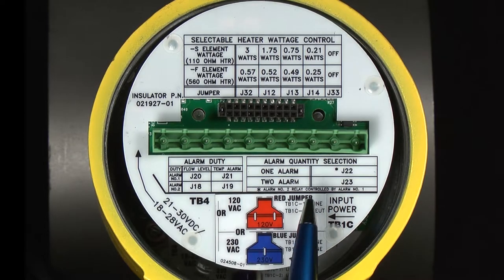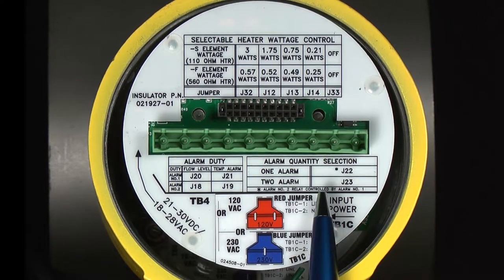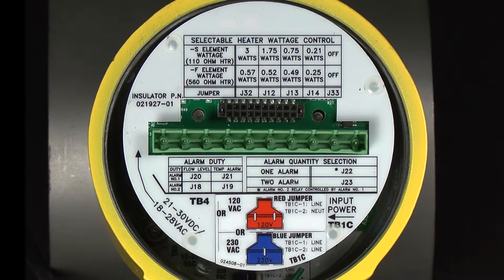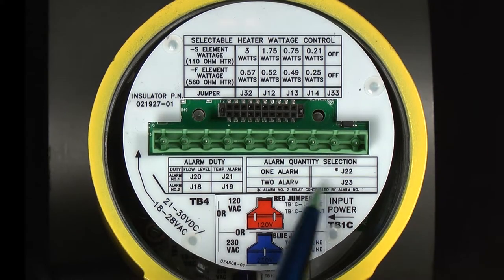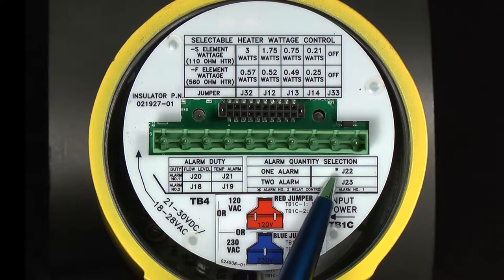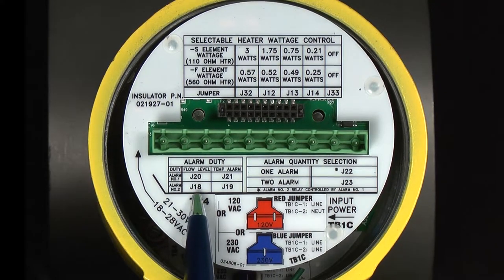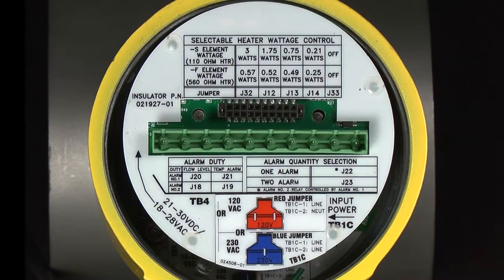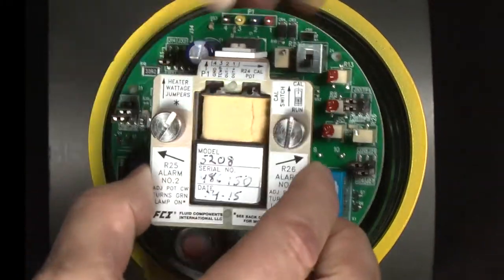The alarm selection, quantity selection section over here, is for determining if you're going to use two alarms or one alarm. There are six amp relays on the circuit board; they're of the form C type, which is the single pole double throw, and they can be set for flow, level, or temperature independent of each other. But if the double pole double throw relay configuration is required, you can use these jumpers to gang the two relays together so that they work simultaneously to control two discrete circuits. So J23 is to have two independent single pole double throw alarms, but if you want one double pole double throw relay, you would select J22. The alarm duty jumpers are used to set the purpose for each relay. For example, you can set both relays for flow or one for flow and one for temperature.